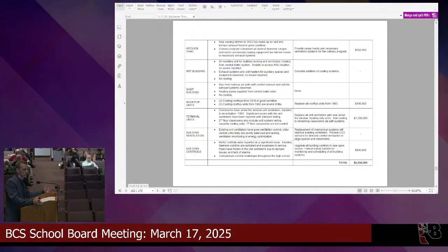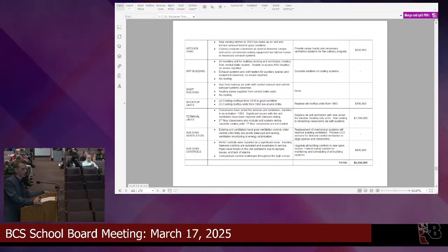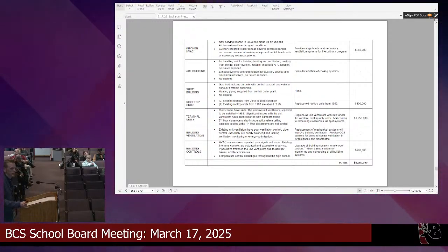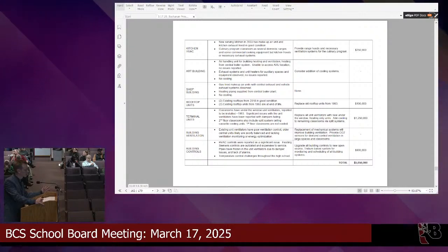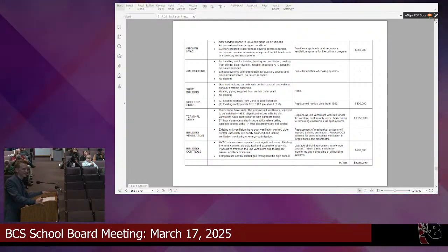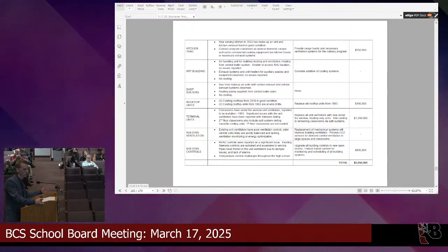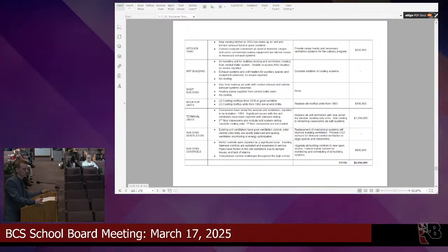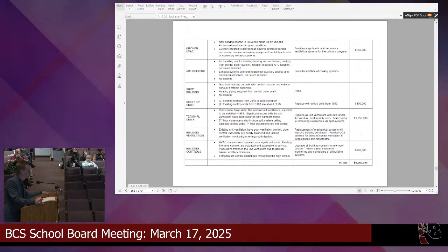Terminal units are a big one - those are your unit ventilators in the classrooms. I think all of the unit ventilators are around 1993, and they've got issues with controls not working, dampers failing, and probably not maintaining temperature, among other challenges. So the recommendation is to replace those unit vents with new ones of a similar style, and continue adding cooling in a similar manner to the remaining classrooms.